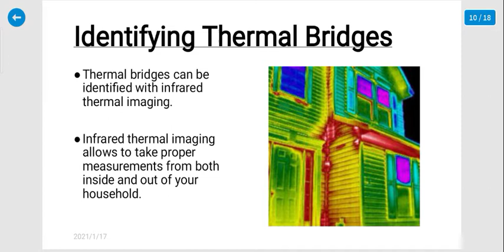Classification of thermal bridges. First, repeating thermal bridges, which are usually evenly distributed over the building envelope and follow a regular path. These are most likely to occur in insulated cold pitched roofs at ceiling joists and insulated suspended timber floor at ground floor joint, timber frame construction, steel wall ties in masonry walls or mortar joint in inner wall leaves.